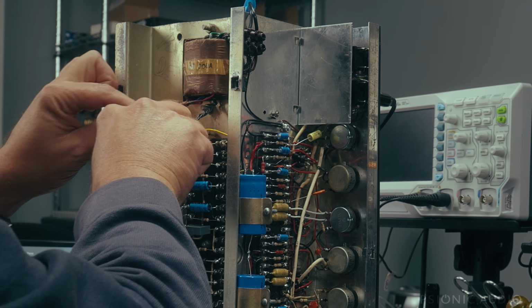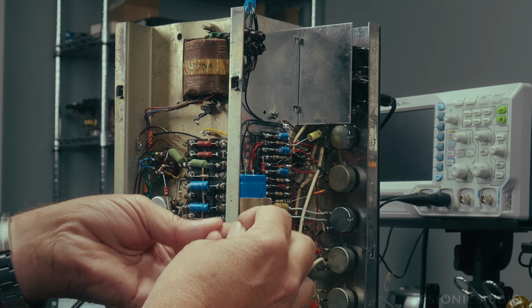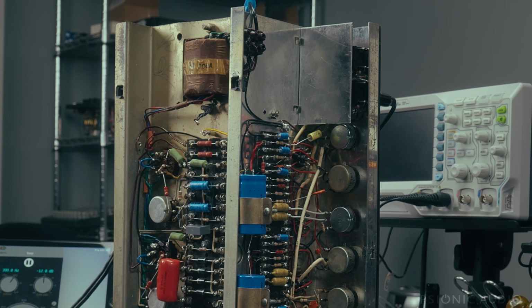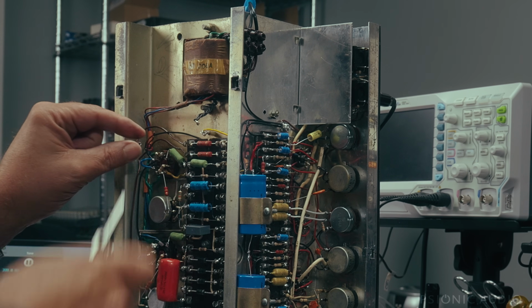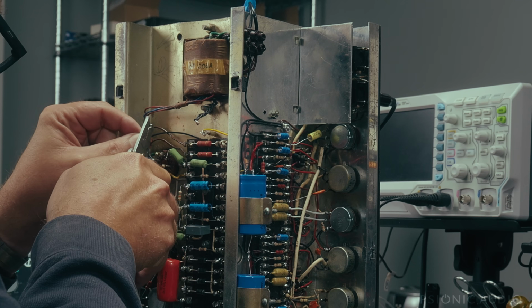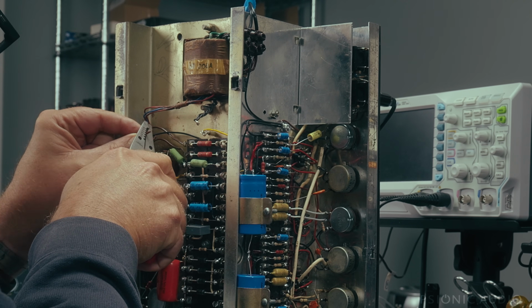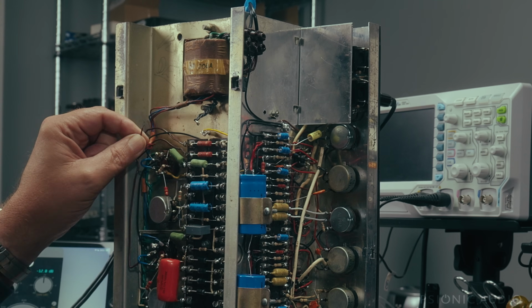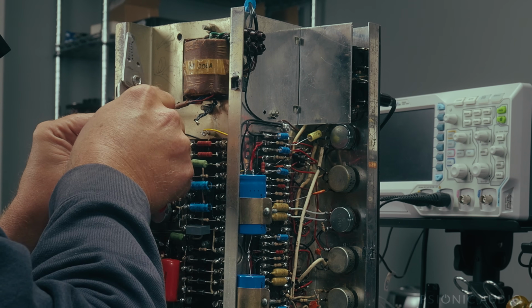And when the old wire gets corrosion on it like that, it kind of creeps up the wire. It's not really trustworthy. And given we had some issues, it might not have been arcing inside the transformer, might have just been arcing as it tried to maintain a connection under current.